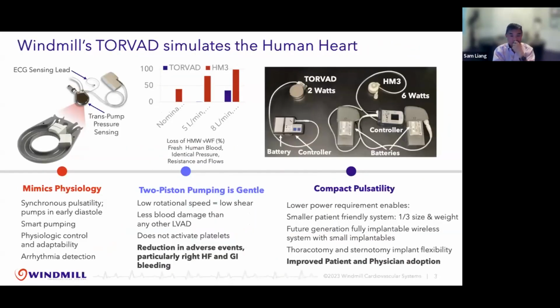Next slide, please. So the solution that Windmill's developed is called the TORVAD, and it's an LVAD that simulates the human heart. The technology up on the upper left-hand side consists of two ceramic pistons enclosed in a titanium case that pumps in a very pulsatile fashion in synchrony with the patient's activities. It has AI algorithms that sense the heart rate, pressure, and several other variables that either speed up or slow down the pump based upon the patient's activity. If the patient's walking fast, it'll speed up. If the patient's sitting, it'll slow down, just like what the human heart does.